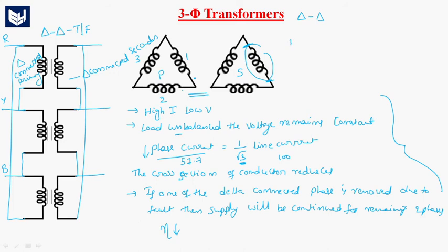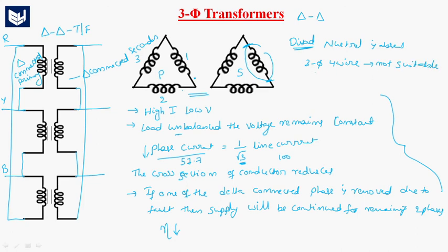The main disadvantage of delta-delta connection is that we don't have a fourth point — that is, the neutral is absent. So this system is not suitable for a three-phase four-wire system, because there is no neutral point. Another point is that the insulation required is more compared to star-star connection. For delta-delta connection, the insulation required is more.